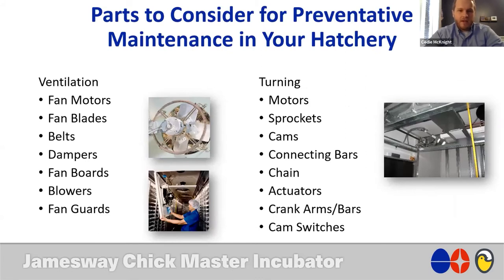More to consider for ventilation and turning. We're going to discuss more upgrades for these, but you still need to manage your fans as regularly as you can. Just because a fan is turning doesn't mean it's working to the level it needs to be. Regularly check those RPMs, even with our newer fans, to make sure they're running where they need to be. The same goes for your belts and dampers. We're all familiar with this, but just as a reminder, these are all things you need to have in your preventative maintenance program, with or without these upgrades.